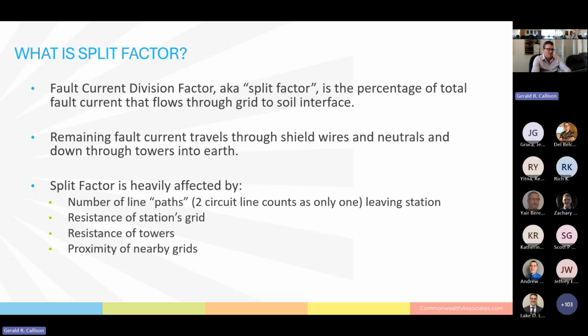And we say paths because if we have a double circuit line, that's where two circuits are sharing one tower, one set of towers, that only counts as one path leaving the station. It's going to be affected by the station's ground grid resistance. If the resistance between the ground grid and remote earth through the soil is very high, then by basic current division, that means that more current is going to go through the shield wires and neutrals down the towers.